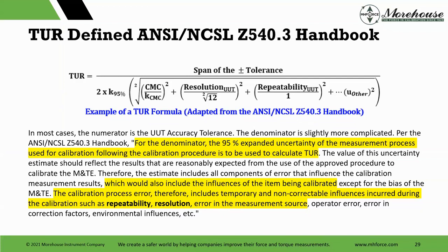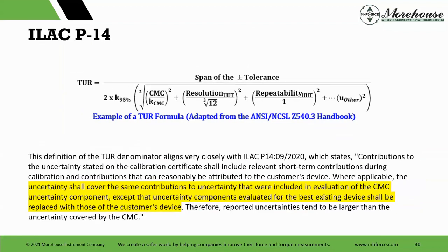However, if we are accredited, we need to comply with ILAC P14. So when we're doing our CMC, our calibration and measurement capability uncertainty, there's a section in ILAC P14 that says contributors to the uncertainty stated on the certificate shall include relevant short-term contributors during the calibration and that can reasonably be attributed to the customer's device. So if we look at that formula for the ANSI Z540.3 handbook, a lot of this should be really wrapped up in the CMC calculation of the different operators and everything else.